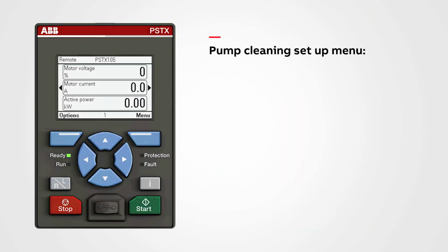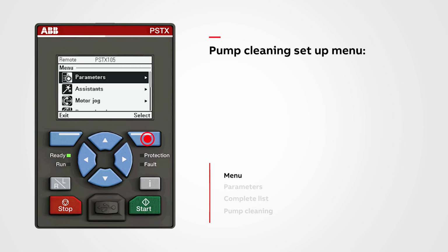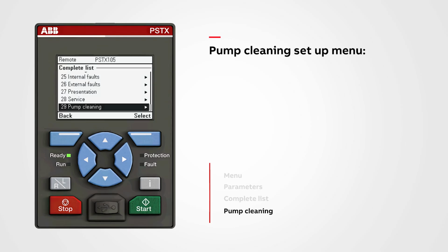Pump cleaning setup menu. So now that we know how to detect a blocked pump, as well as what two modes to use to resolve it, and what a pump sequence looks like, let us look at how to set up the pump sequence in the PSTX Softstarter. Go to the pump cleaning setup menu by entering the menu. Select parameters. Enter the complete list. Navigate to section 29, pump cleaning.